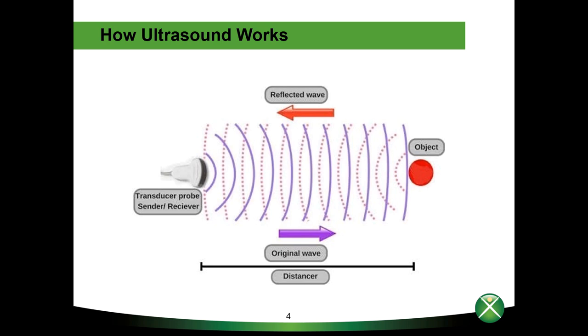A signal, or ultrasonic sound waves, are sent from a source — in this case the transducer probe — toward an object. The sound waves are generated somewhere between 2 and 20 megahertz, which cannot be heard by the human ear. For context, audible sound waves are between 20 and 20,000 hertz. The sound waves bounce off the object and return to a receiver. Depending on the transmission ability of an object, the sound waves may transmit through some areas or reflect back in others, allowing the receiver to provide information to the computer to formulate an image.